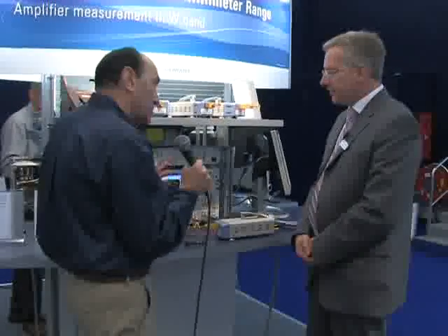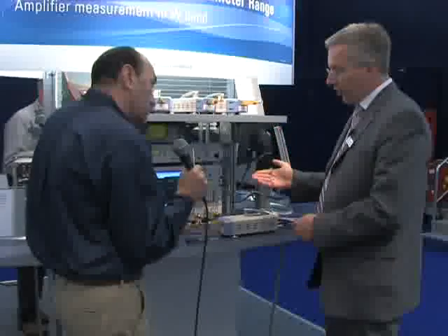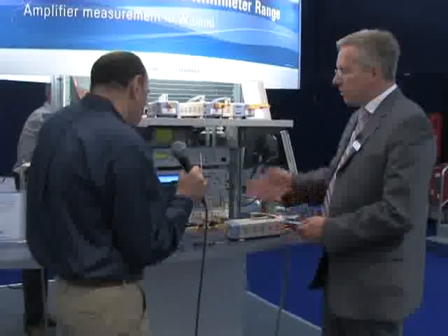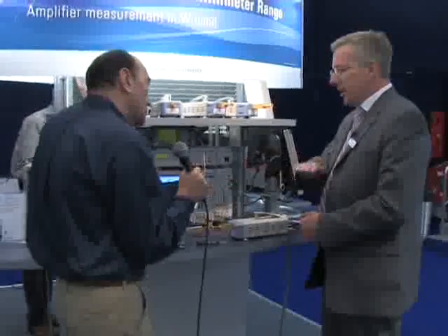What are the specific applications? First of all, the amplifier measurements, as we can see here, with especially the compression point measurement electronically controlled. It is also possible to do a power calibration, and the power calibration allows to make the generator flat, so we can use it also for other devices as well.